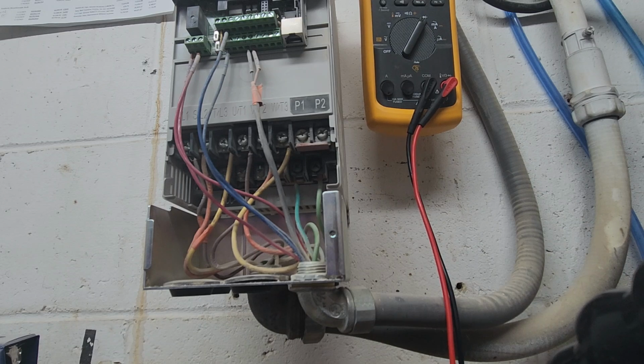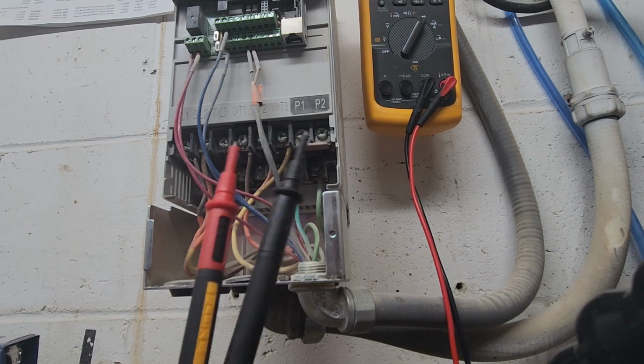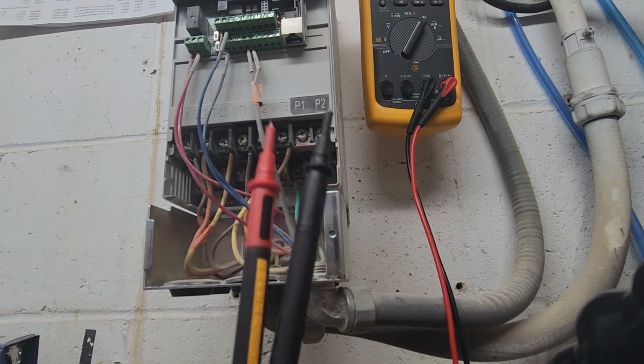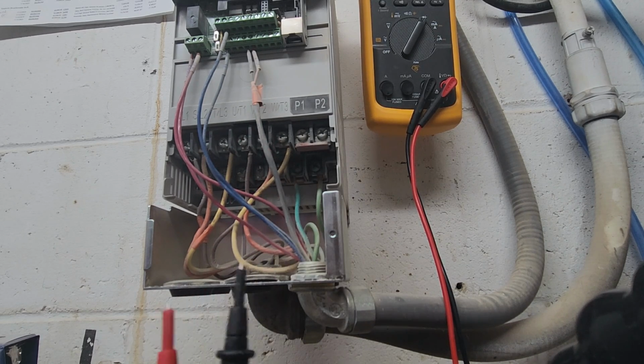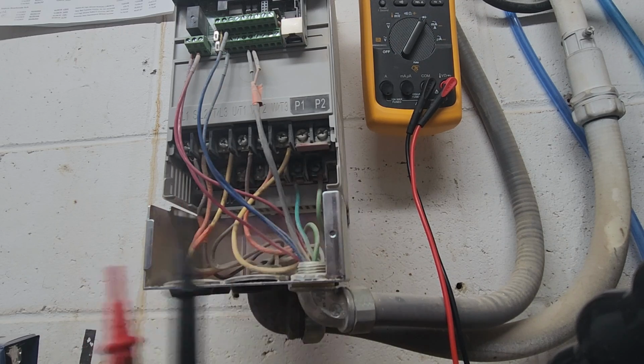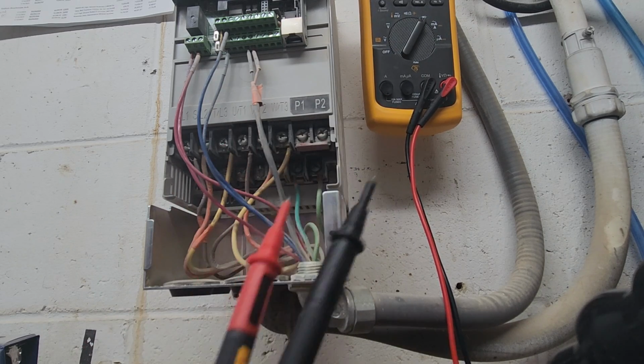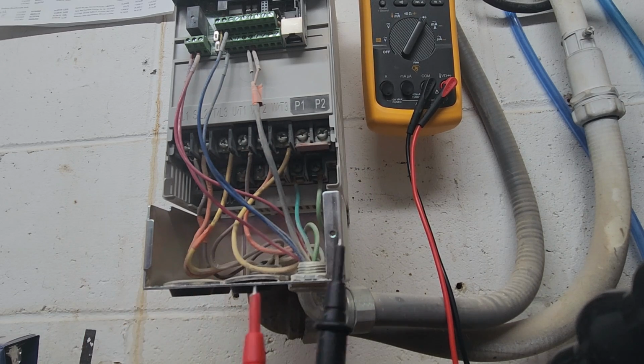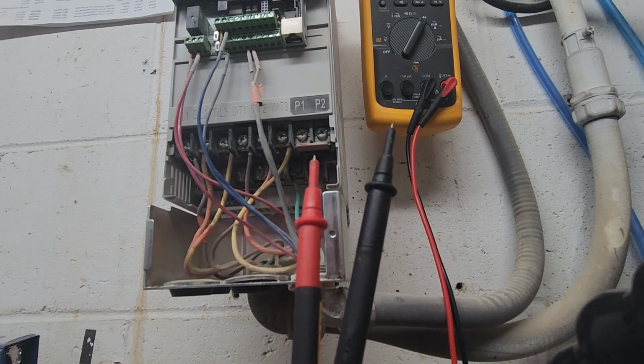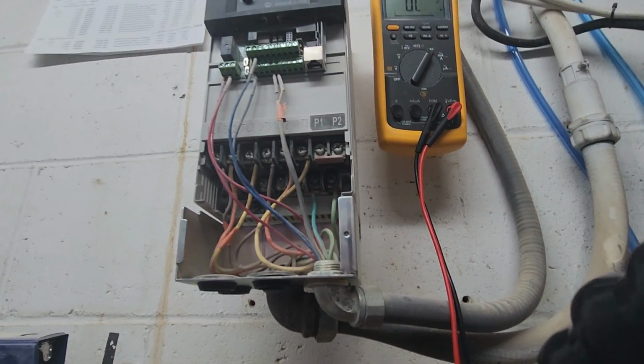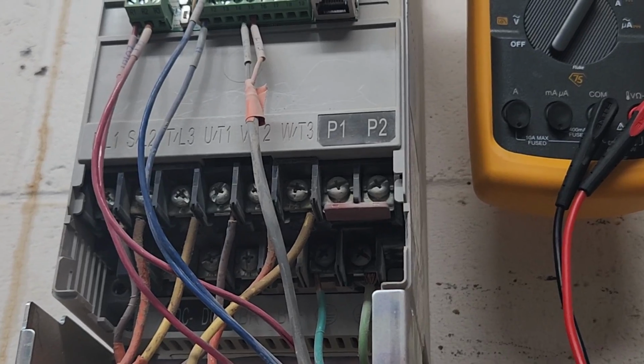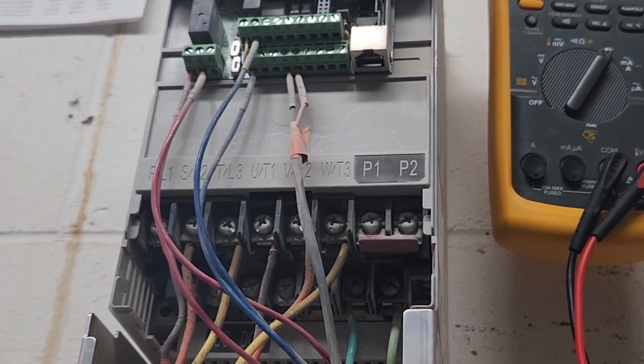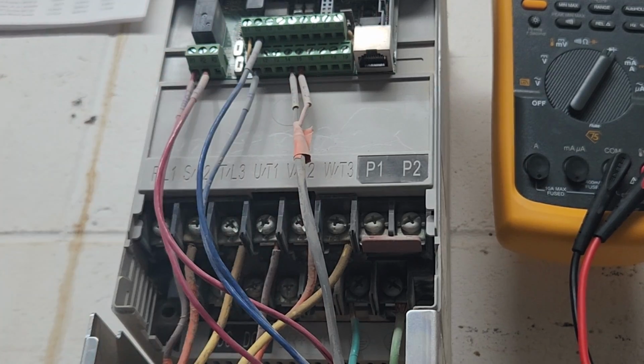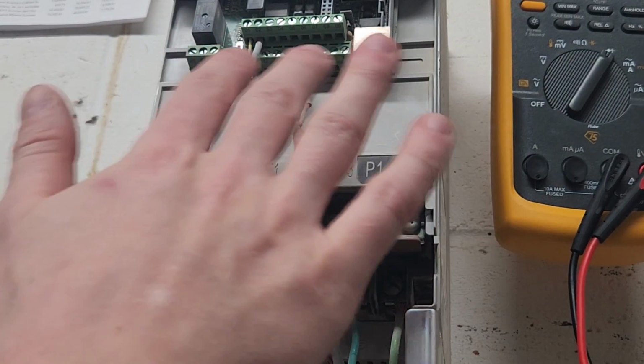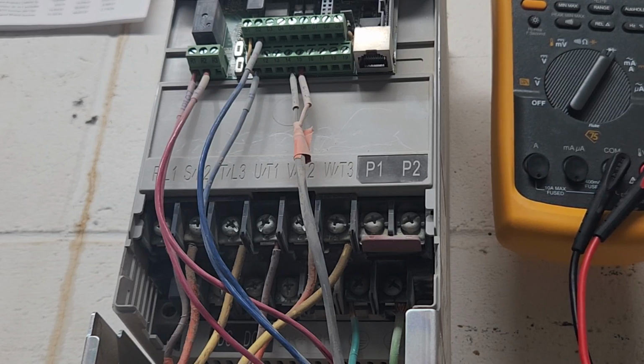Another thing to consider is if you're aware of how your VFD is receiving a signal to run at whatever speed. Let's say, for example, you are modulating your frequency on your variable frequency drive, auto tuning it using a PLC or a potentiometer on a switch somewhere. Let's say you're using a 4 to 20 milliamp signal. You should be able to look for that up here on your control module somewhere. Or if you're using 110 volt or a variable voltage signal, like a 0 to 10 volt signal, you should be able to get those readings up there. That's super dependent on how you have your whole system set up, and I probably couldn't help you with that.